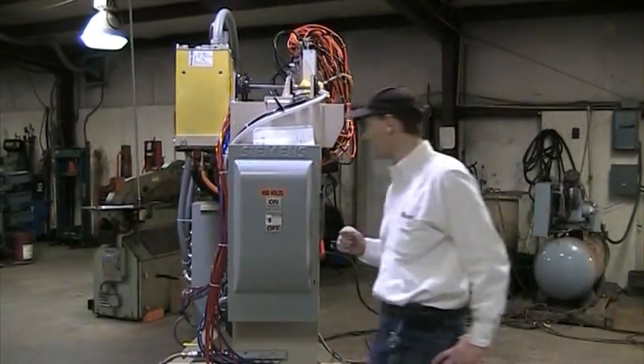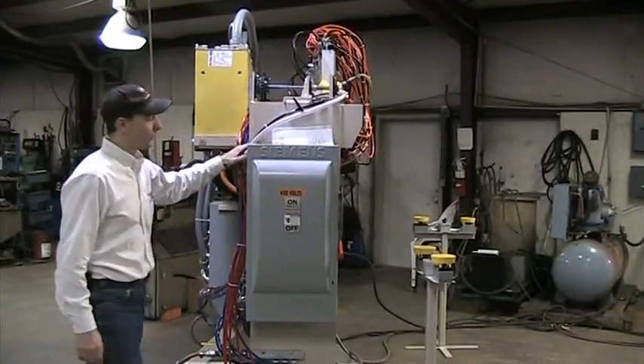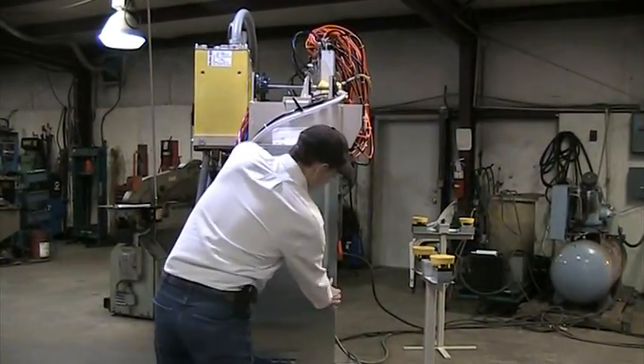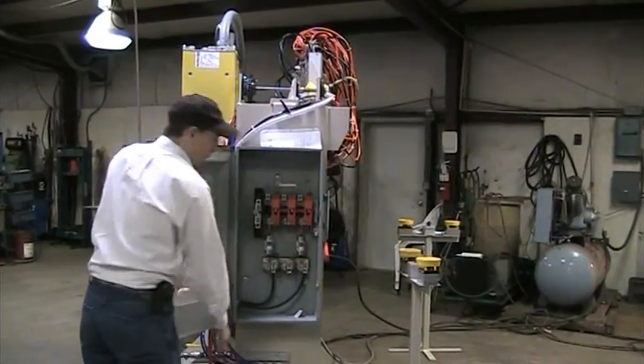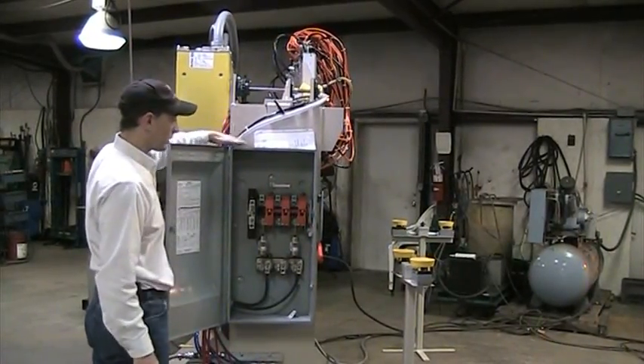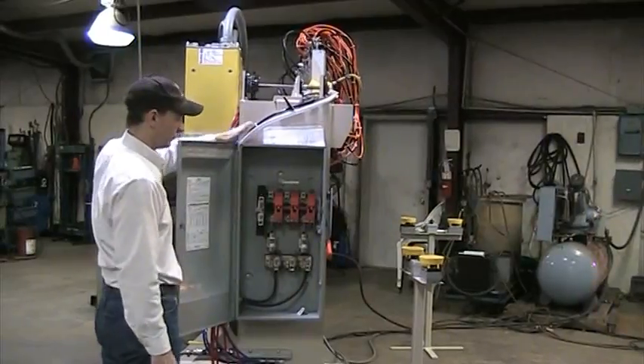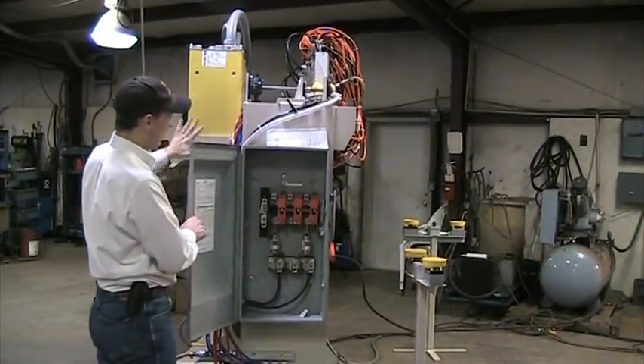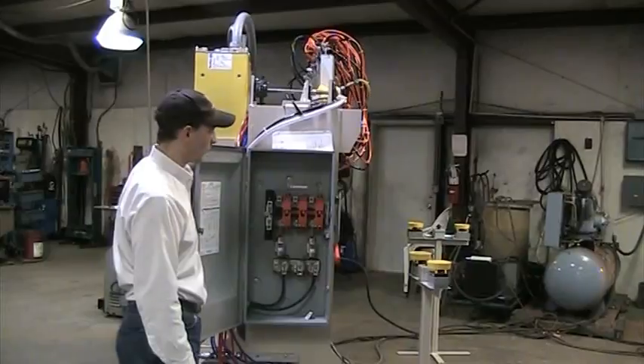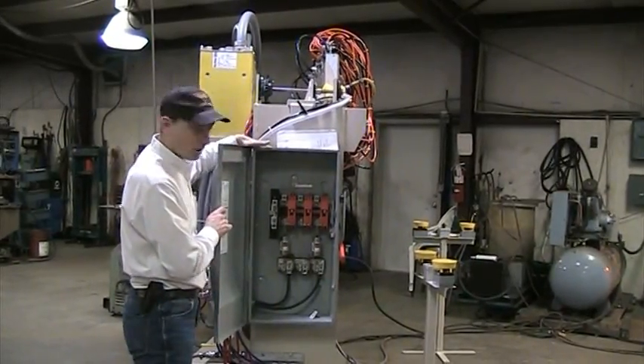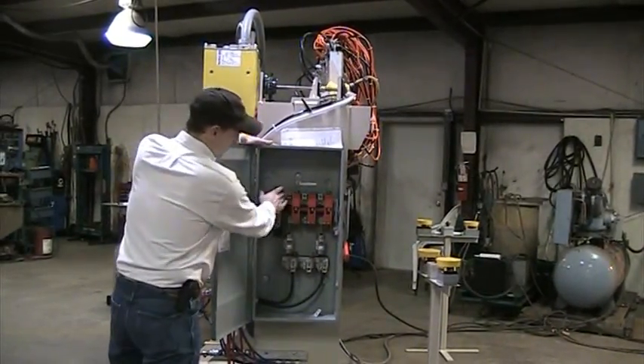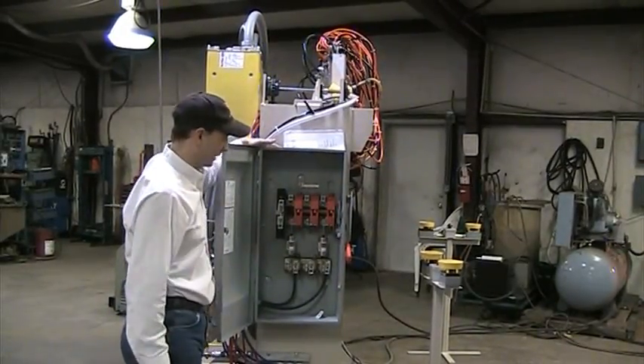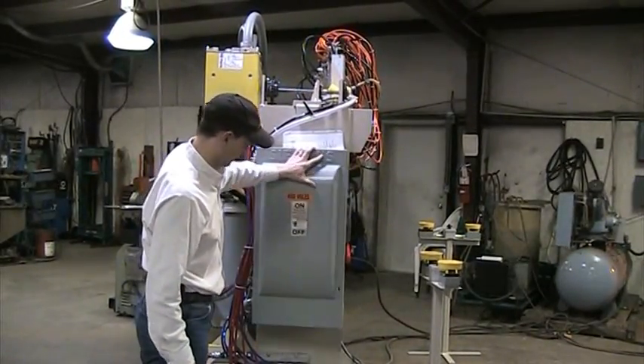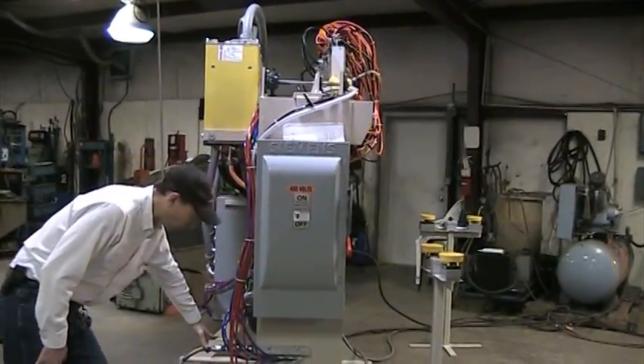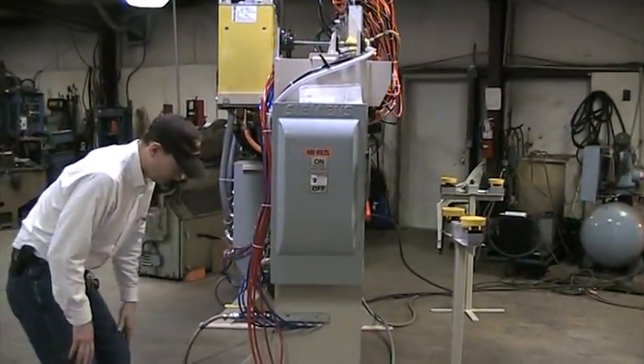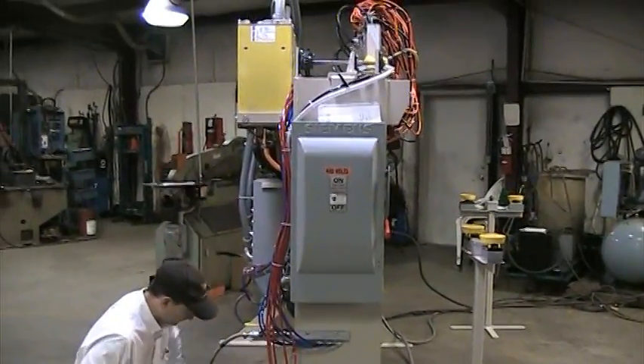Okay, we're now on the left-hand side of the machine. This is where you're going to run your power into this disconnect. It's already got the appropriate fuses in it. It's wired up. Because we didn't know where you're going to run your power in, we haven't popped any holes in the box. There are knockouts all the way around as a standard disconnect box. And we've just run power into the actual control cabinet itself. So when you get this machine, knock out the appropriate hole, run your power in, and connect to the outboard 2 connections on the line board itself. Down below, you've got a water in, which is marked by the blue water, water out, which is marked by the red water.